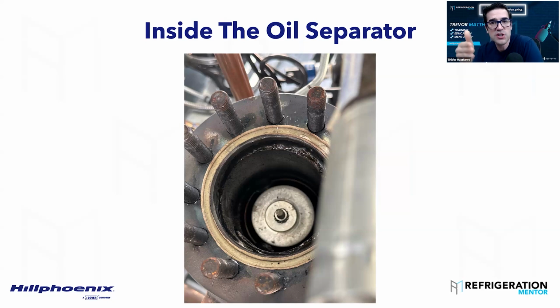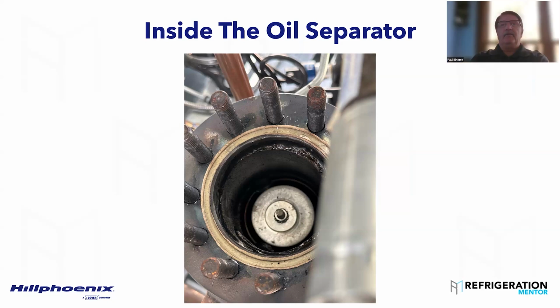Why don't we say the checks that you do, the way you do it, because it's different than the way other people do it. Yeah, the way I do it is we fill the oil reservoir between the second and third vacuum, just like you would any other startup. You put your suction line filters in. Nothing changes, but we're not going to put any oil in the compressors. We're going to isolate it in the reservoir. And once I get on site, we're going to go through all our checks, as Trevor just mentioned, and then we're going to see stuff work.